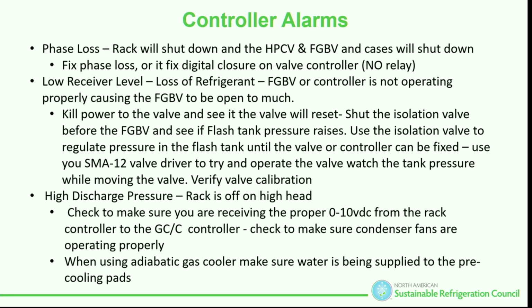Check to make sure the fans are running. Make sure I'm getting the proper speed signal from my controller. It's going to be a 0 to 10 volt signal to my adiabatic, or my ECM motors. ECM, did I just say ECM motors? So I basically said electrically commutated motors. Is that what I just said? I'm an idiot. Alright, sorry.